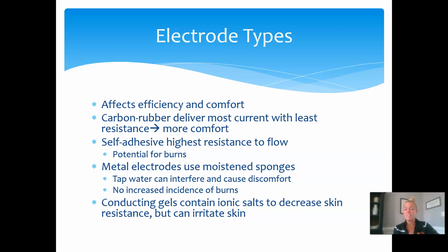It is usually because of the adhesives, and what happens is you pull them off the patient when you're done with treatment, and off comes some dead skin cells and hair cells and some oils and things like that. And then every time they're reused, that happens over time, that starts to build up, and then we can actually develop some hot spots. So again, when you realize that your electrodes aren't sticking so well, swap them out for a new pair.